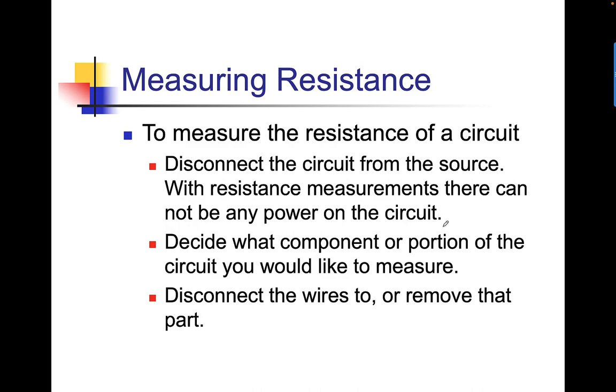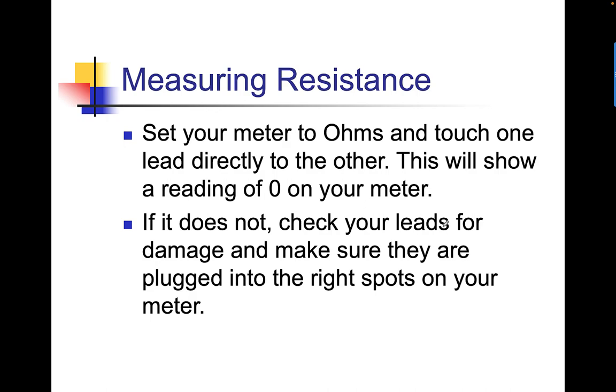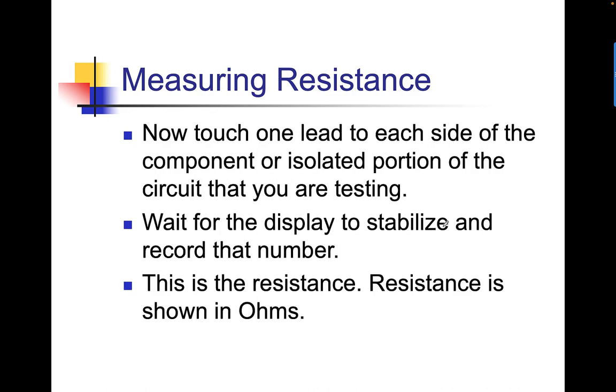To measure resistance of a circuit, this is extremely important: disconnect the circuit from the source. With resistance measurements, you cannot have any power on the circuit — you'll break your meter. Decide what component or portion of the circuit you want to measure. Disconnect the wires to and remove that part. You can only take resistance of components if they're isolated. Set your meter to ohms and touch one lead directly to the other — that should show a reading of zero on your meter. If it doesn't, check your leads for damage and make sure they're plugged into the right spots on your meter.